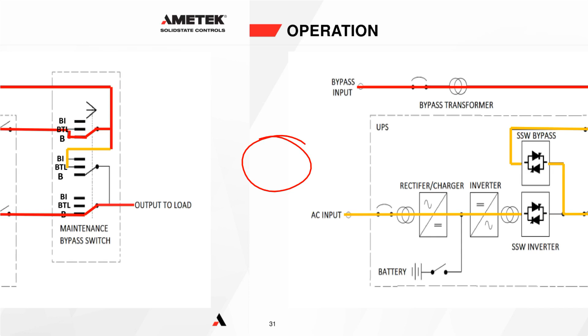So once you have pressed bypass to load on the static switch, then we can actually physically move the switch to the bypass to load contact, which is this middle contact here. And what that does is, remember, it's make before break. So it actually makes this red line here go down through this contact, and out to the loads before breaking this contact here. Okay, so it makes this contact and then breaks this contact. And at that point, the red on the screen here is the power flow. All of this is energized, but it's now no longer supplying any power to the loads whatsoever.